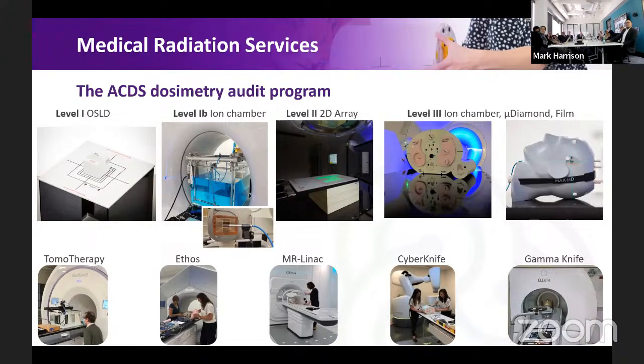The top far right is what's called a level 3 audit, that's end-to-end. So ARPANSA sends out one of its phantoms, it is CT'd by the facility. They put a plan on it according to the guidelines provided by ARPANSA, and then a team goes out from ARPANSA and measures it. And again, the test is whether the facility is delivering the amount of radiation they think they're delivering in the context of that dose.